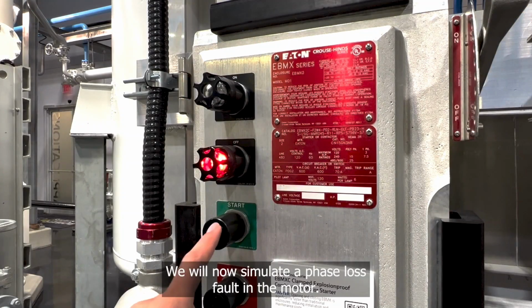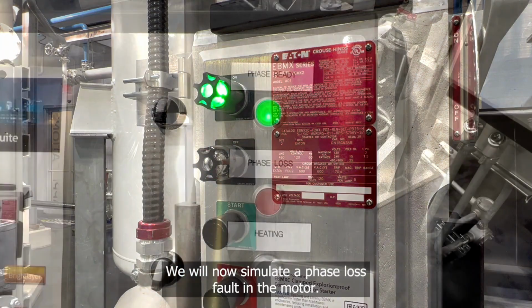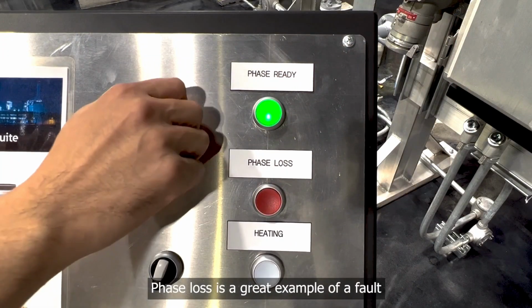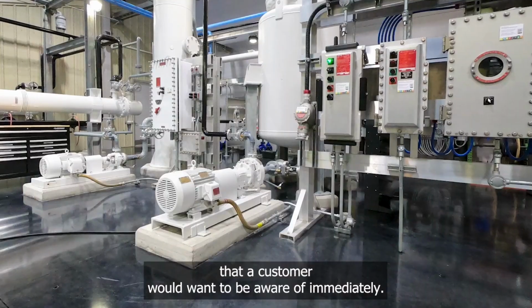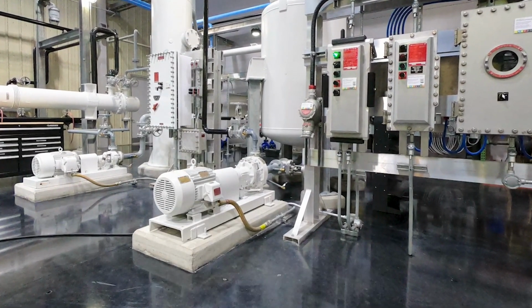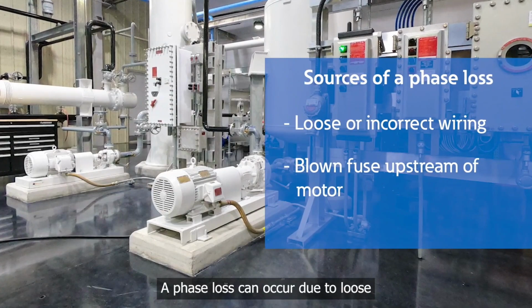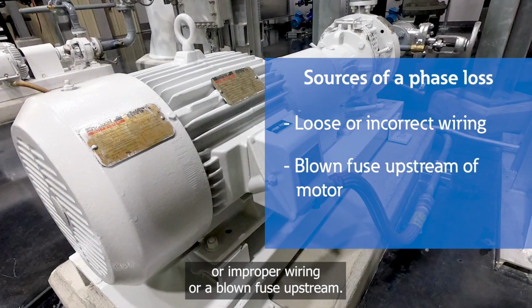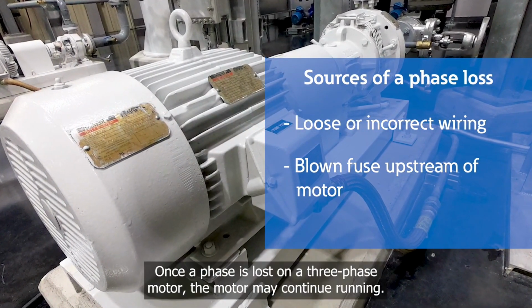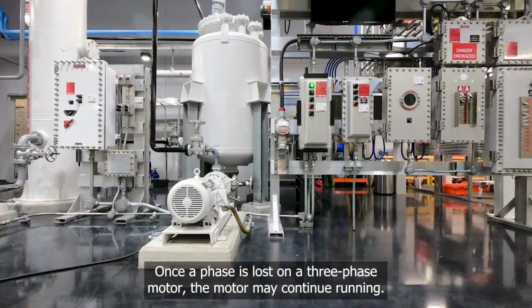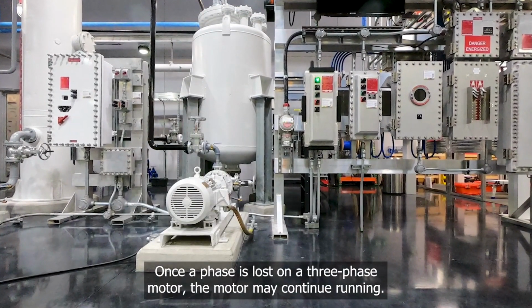We will now simulate a phase loss fault in the motor. Phase loss is a great example of a fault that a customer would want to be aware of immediately. A phase loss can occur due to loose or improper wiring or a blown fuse upstream. Once a phase is lost on a 3-phase motor, the motor may continue running.